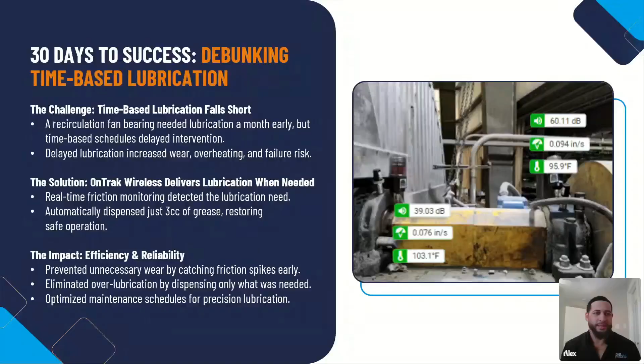All right, here's another one. Like a lot of facilities, environment can be an issue, whether you're in Eastern Canada where it gets frigid half the year, or in Texas, my home state, where 112 degree days aren't abnormal. We were working with a facility dealing with fans that face extreme heat, and they were finding a lot of failed bearings. They were on a time-based lubrication method, and they said, we want to find a different solution.